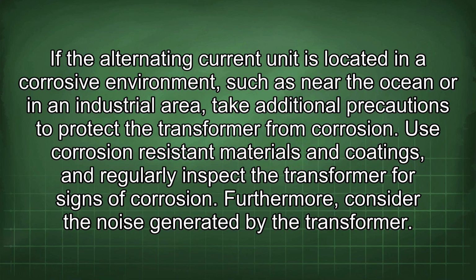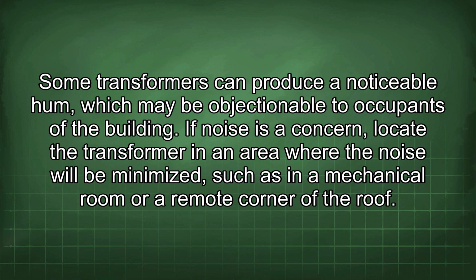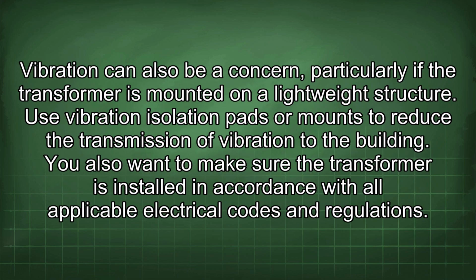Furthermore, consider the noise generated by the transformer. Some transformers can produce a noticeable hum, which may be objectionable to occupants of the building. If noise is a concern, locate the transformer in an area where the noise will be minimized, such as in a mechanical room or a remote corner of the roof. Vibration can also be a concern, particularly if the transformer is mounted on a lightweight structure. Use vibration isolation pads or mounts to reduce the transmission of vibration to the building.